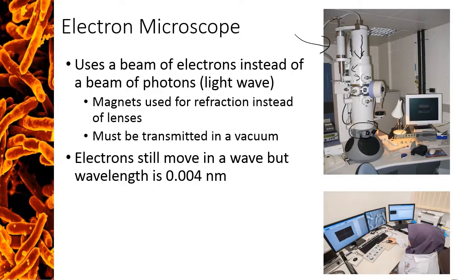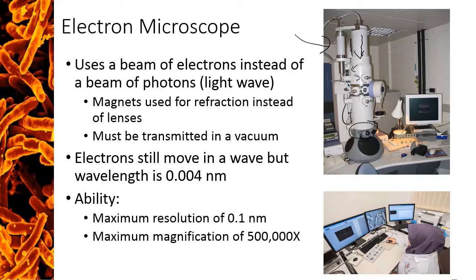However, the wavelength of a beam of electrons is much smaller, at about four thousandths of a nanometer. If you remember the equation for resolution, a wavelength this tiny means that the electron microscopes have a much higher resolving power and allow you to see very detailed images. In fact, the maximum resolution of an electron microscope is about 0.1 nanometers, while the maximum magnification is about 500,000 times.